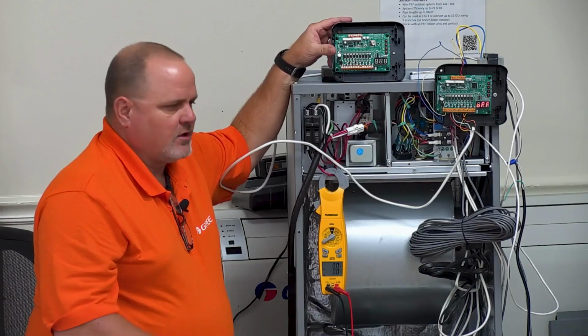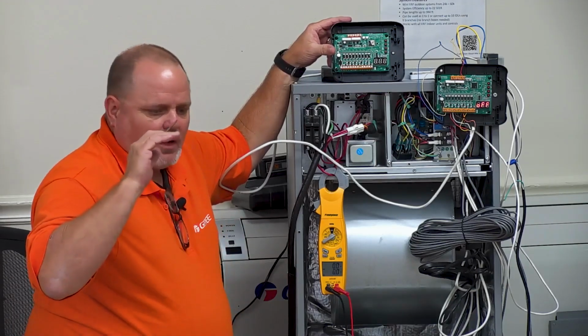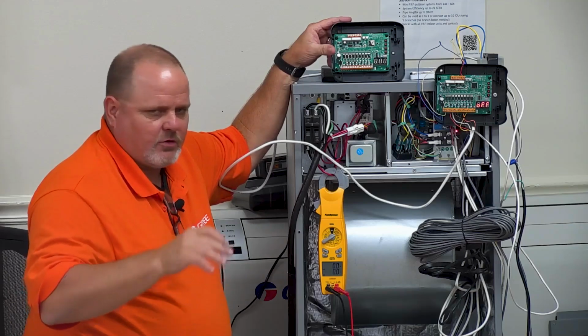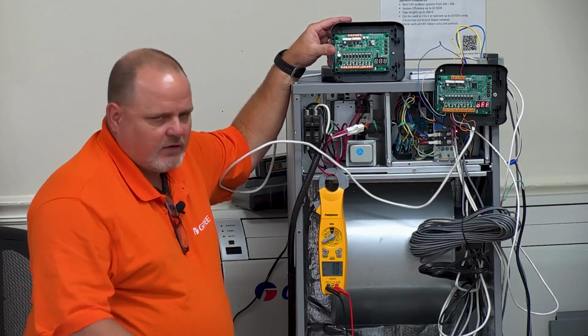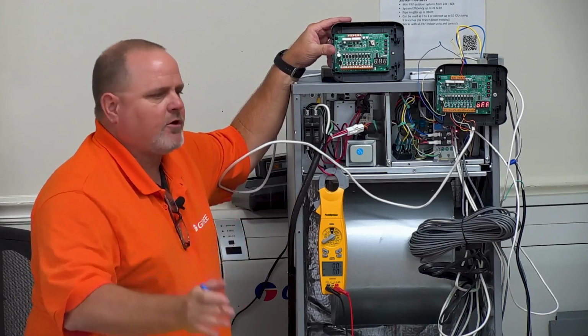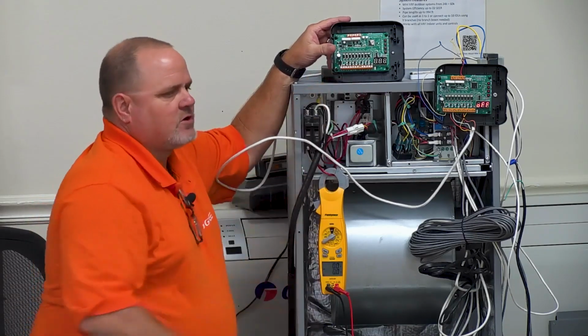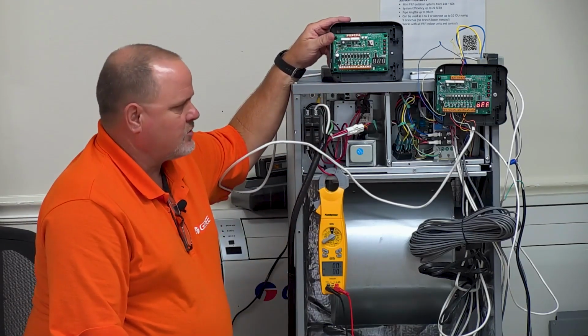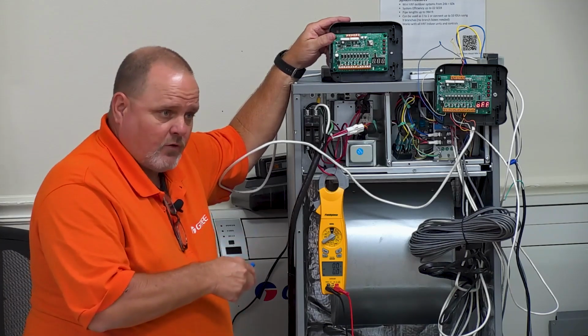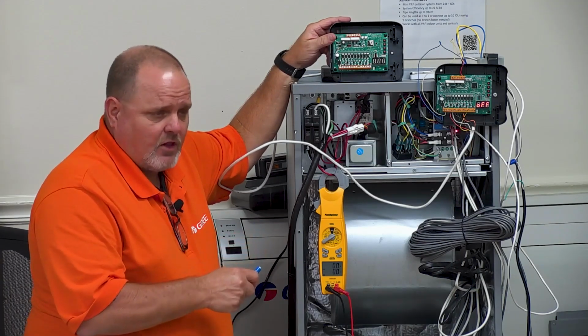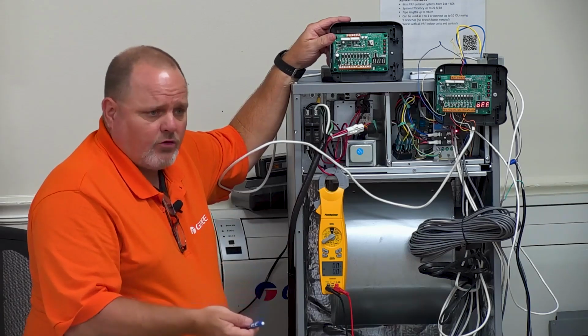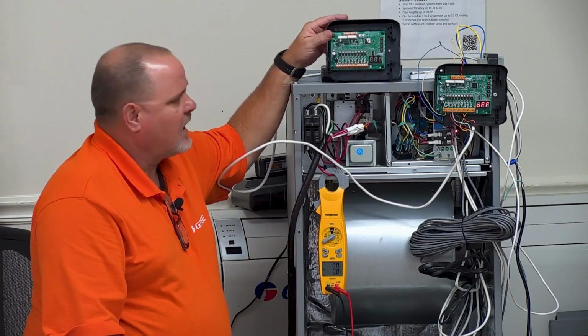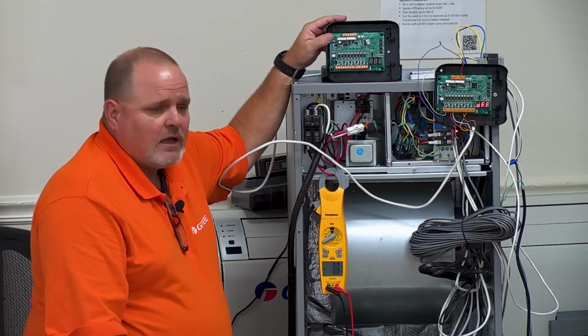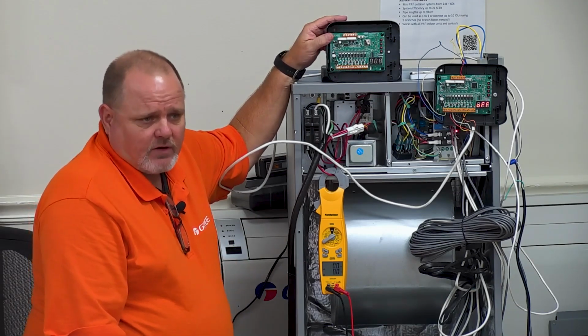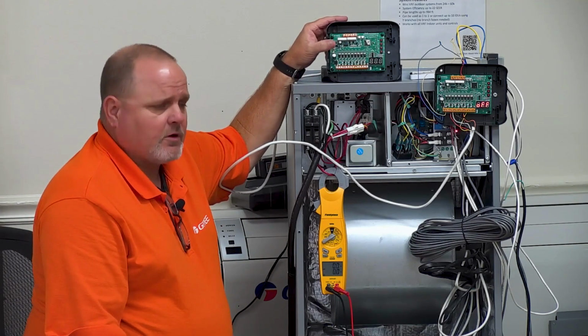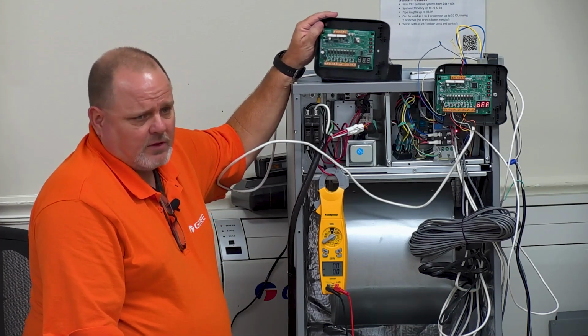This gives you the ability, if you want to use an Ecobee thermostat, a White Rodgers thermostat, a Honeywell thermostat, even a Nest thermostat, whatever heat pump thermostat you want to use, to tie that third-party thermostat into it. Again, like I said, we had a 24-volt adapter before. We still have it available, but that uses just a heat-cool thermostat, not a heat pump thermostat. I don't have the part number for you yet. It'll be coming out soon, and we will have an announcement about the new 24-volt adapter, what the part number will be, and that will be the new heat pump 24-volt adapter.